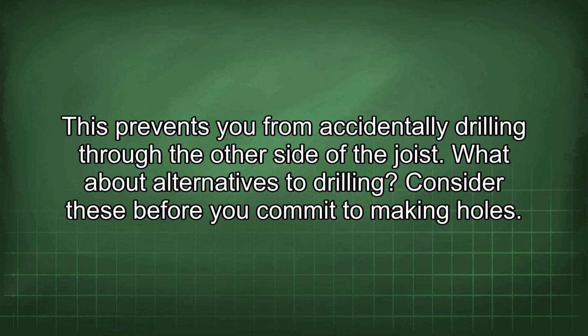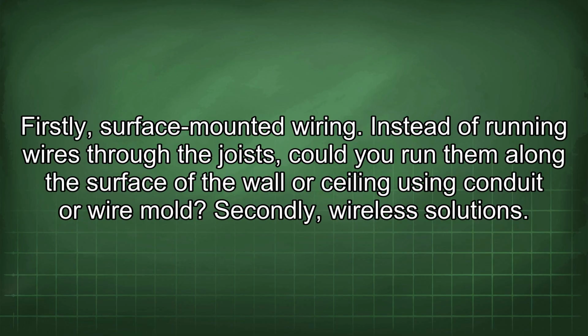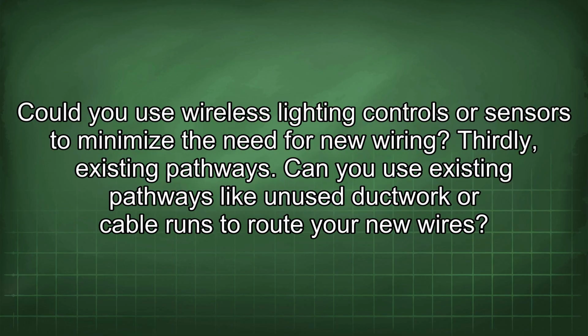What about alternatives to drilling? Consider these before you commit to making holes. Firstly, surface-mounted wiring. Instead of running wires through the joists, could you run them along the surface of the wall or ceiling using conduit or wire mold? Secondly, wireless solutions. Could you use wireless lighting controls or sensors to minimize the need for new wiring? Thirdly, existing pathways. Can you use existing pathways like unused ductwork or cable runs to route your new wires?